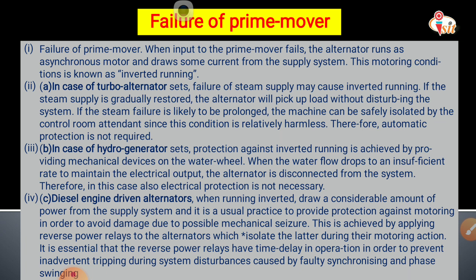For a diesel engine in an inverted running condition, protection is achieved by applying a reverse power relay to the alternator, which isolates the machine during motoring action. It is essential that the reverse power relay has a time delay in operation to prevent tripping during system disturbances caused by faulty synchronizing.